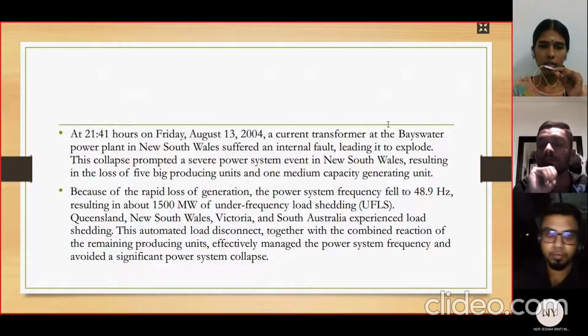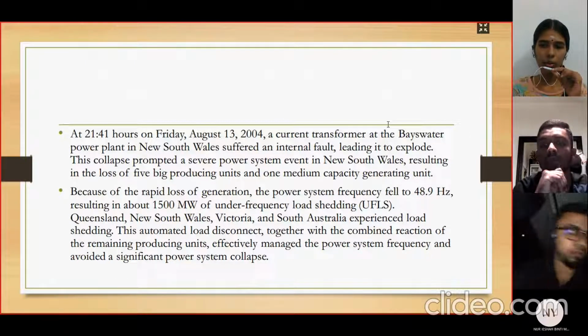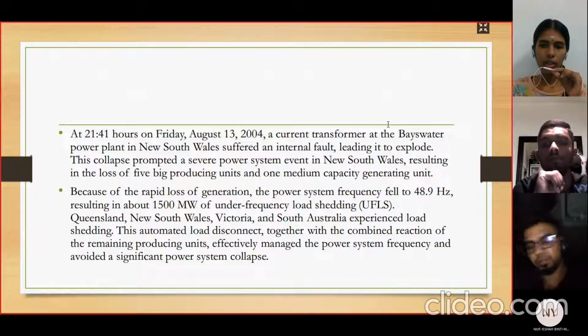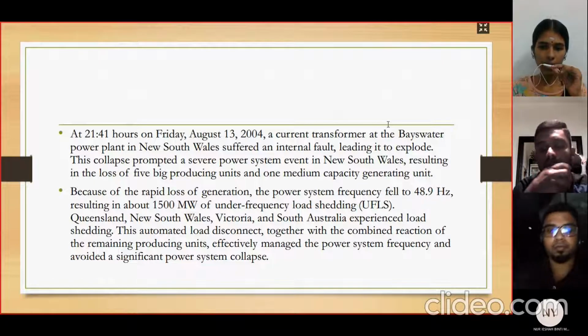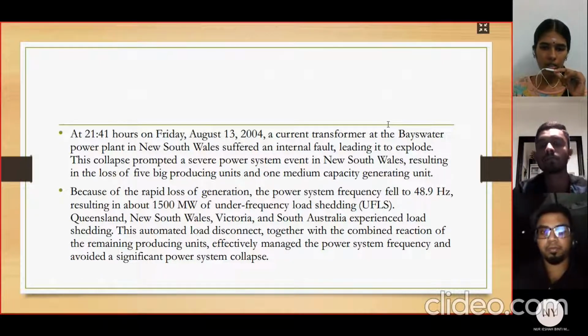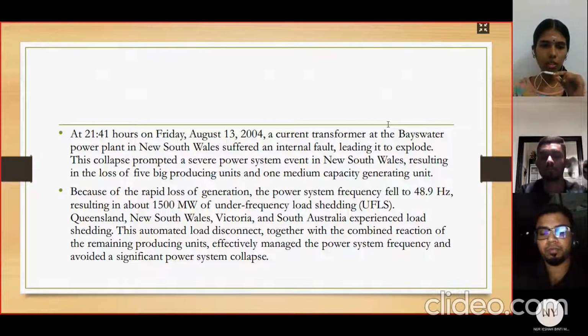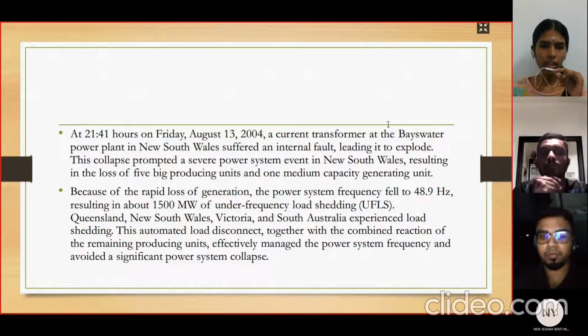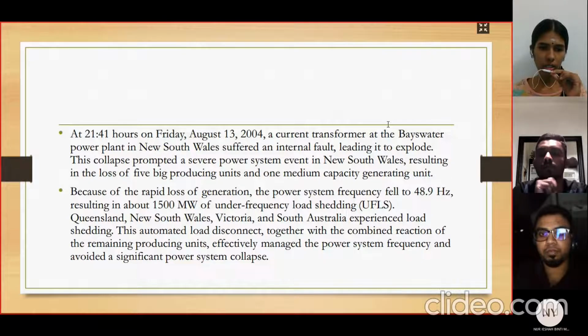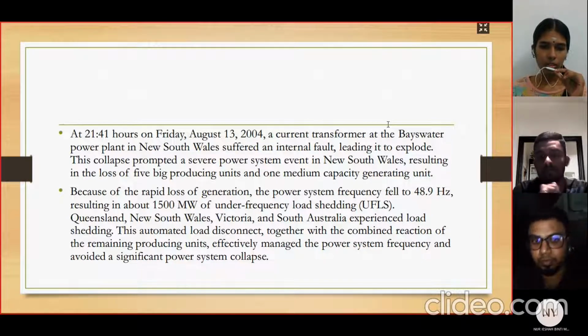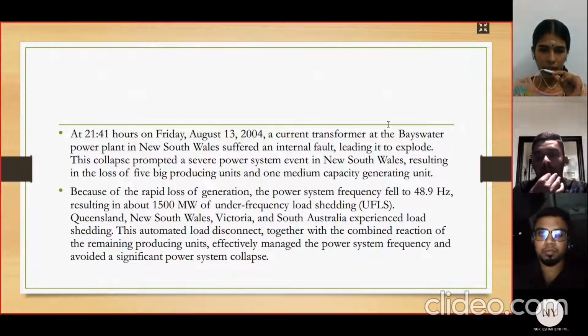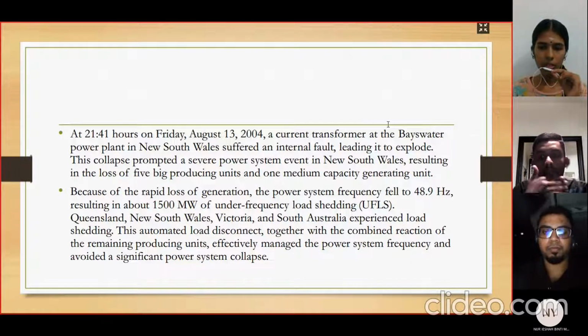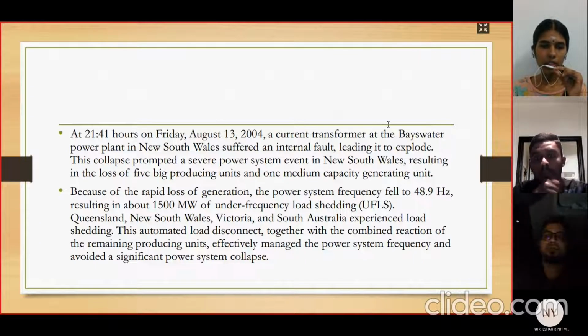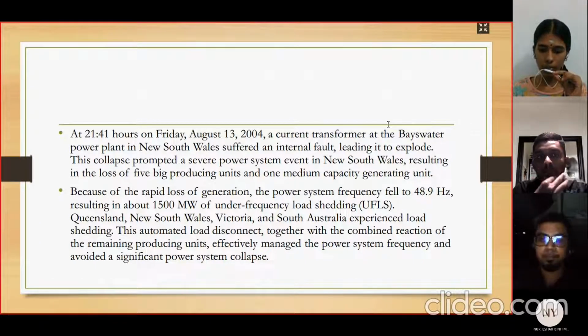Because of the rapid loss of generation, the power system frequency fell to 48.9 Hz, resulting in about 1500 megawatts of under frequency load shedding. Queensland, New South Wales, Victoria, and South Australia experienced load shedding. This automated load disconnection, together with the combined reaction of the remaining producing units, effectively managed the power system frequency and avoided a significant power system collapse.